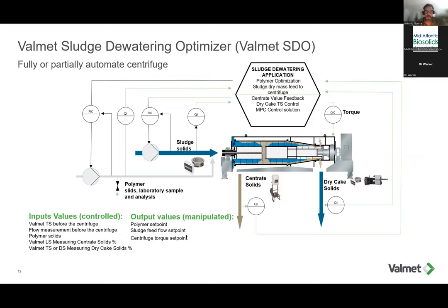Taking all those variables, what we call control input values, we're able to enter all that into a model predictive controller, which will optimize or control what we call the manipulated variables, which would be controlling your set point polymer, changing it in real time, and controlling your feed flow. So we need to slow things down or accelerate things to keep the optimization as efficient as possible, as well as controlling the torque set point. So using measurements in a model predictive controller, you can basically automate the entire system.